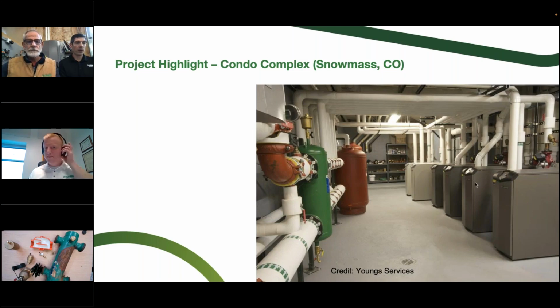So this is a project that I worked on when I was a rep for Caleffi in Colorado, and they were able to address a lot of these things that we've talked about with a hydro separator, combining the air and dirt separator, still in the proper place for both. The return is going to come back here before we get to the boiler pumps and the heat exchangers. We're going to catch the dirt there, and then the hottest, lowest pressure spot, before we boost back up with the system pump, is going to be right here. So we're going to separate air and dirt really well.